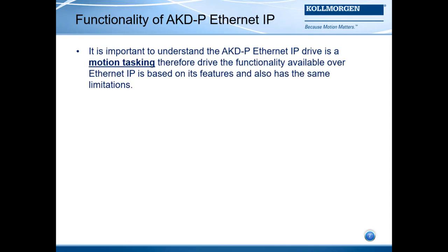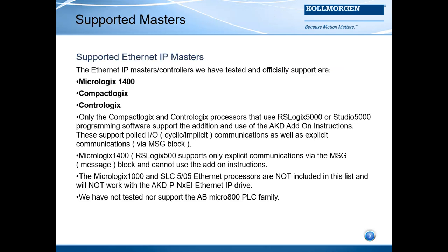It is important to understand that the AKD-P Ethernet IP drive is a motion tasking drive. Therefore, the drive's functionality available over Ethernet IP is based on its features and also has the same limitations. We are often asked what Ethernet IP masters we support. The Ethernet IP masters or controllers we have tested and officially support are exclusive to Allen Bradley. That is the MicroLogix 1400, CompactLogix, and ControlLogix.